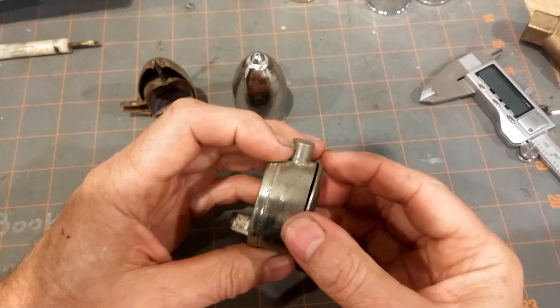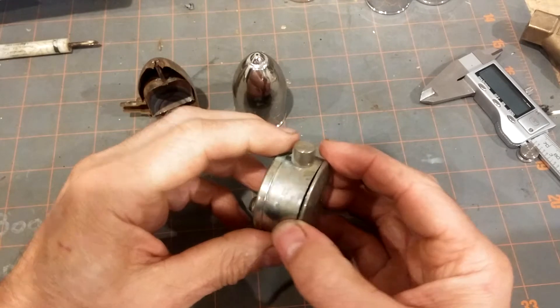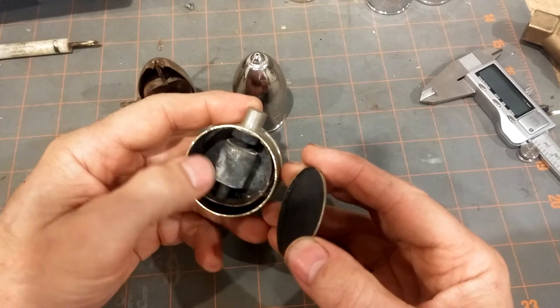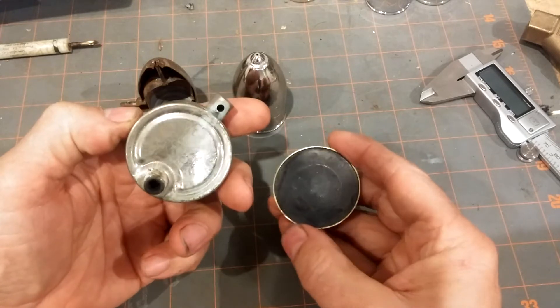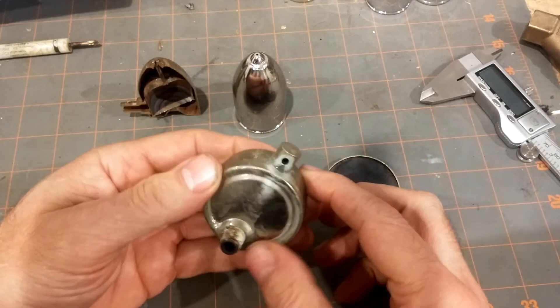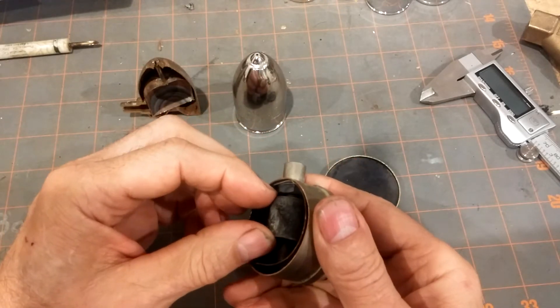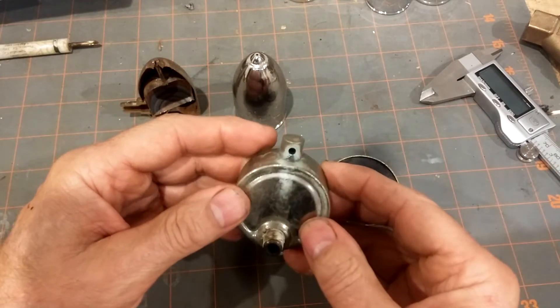The vent itself is very well constructed. Soldered connections are used throughout — it's all metallic construction and generally a very rugged vent. Usually people tend to buy a big hole, and what happens is it starts to fill up with minerals and eventually begins to leak, and then people blame the vent.